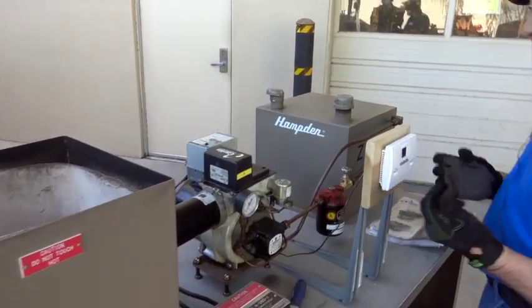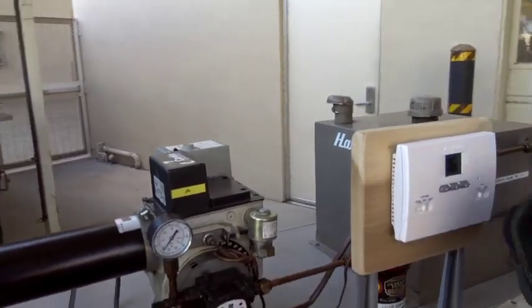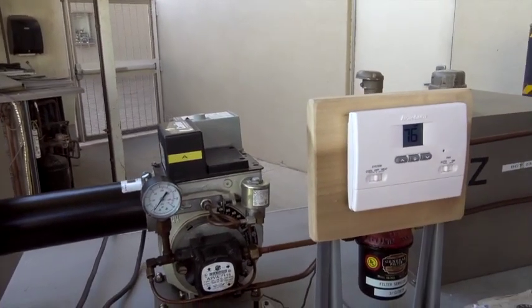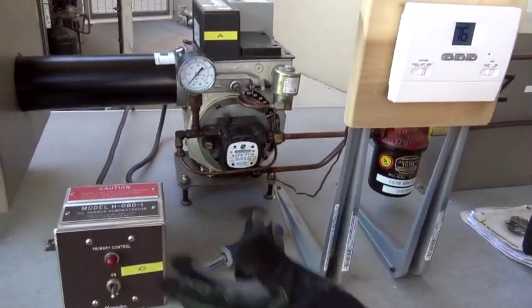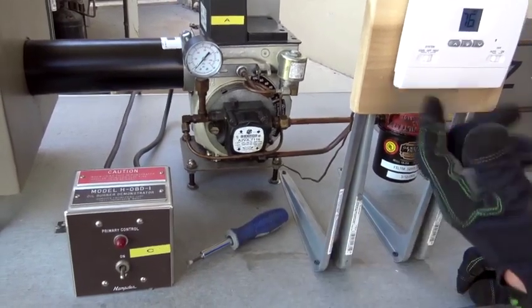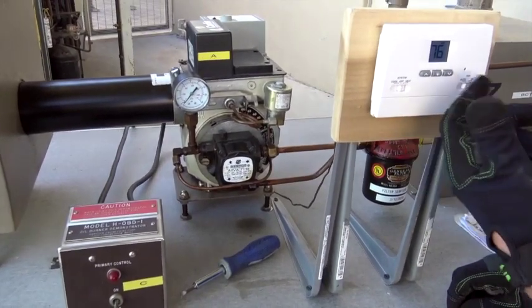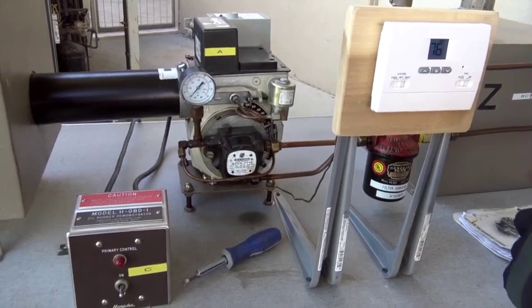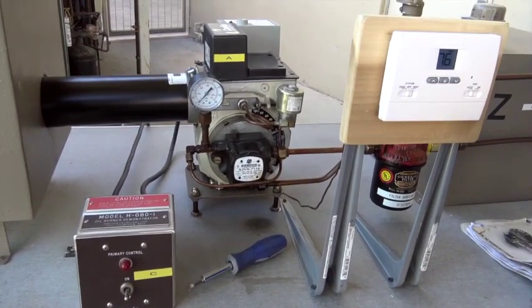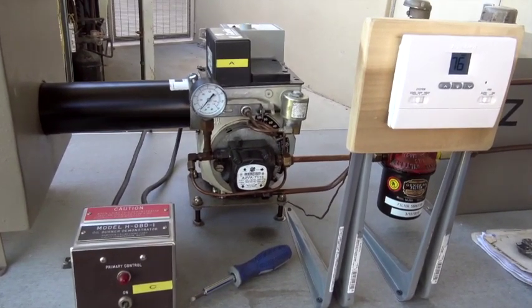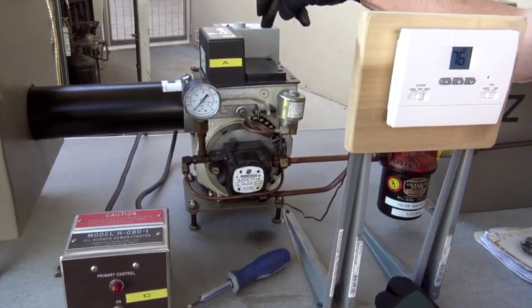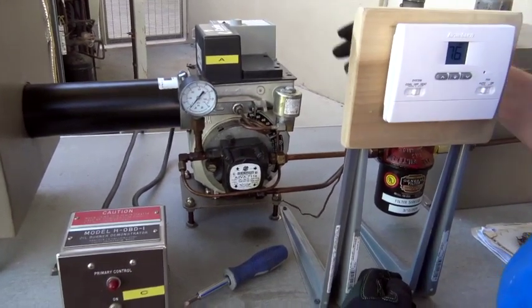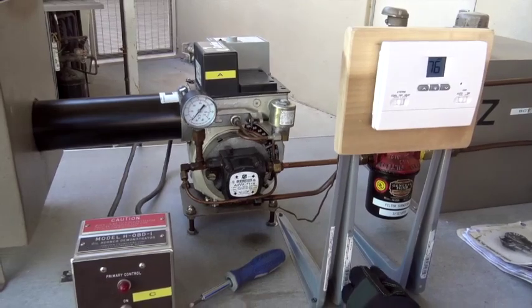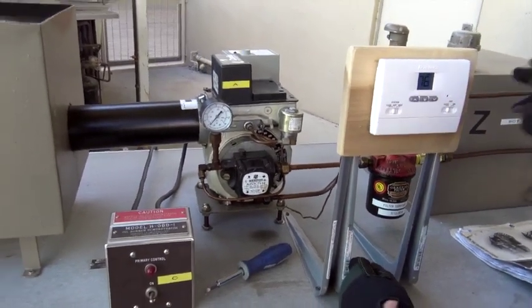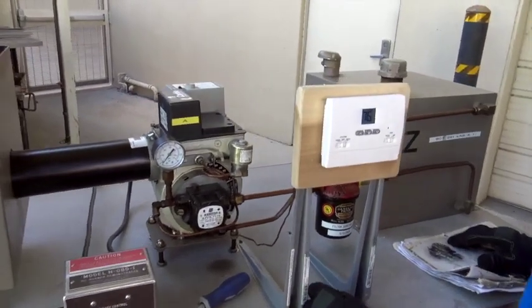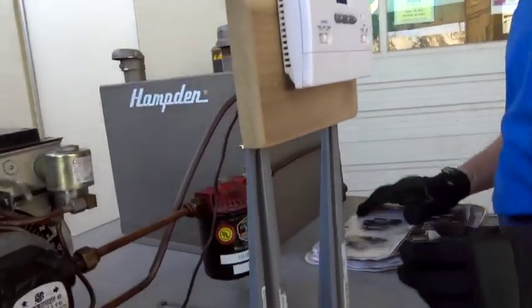Now this is our thermostat, which operates everything here. Naturally, you understand thermostats. That's our on-off control switch, primary control switch. We're eventually going to set this to heat. It's an electronic thermostat. We're going to set it above the set point to get this thing fired up, and that's going to send the signal to the control board. We're ready to go. It's going to start up the combustion air, and off we go. But I'm going to do a little bit on the fuel now, the most important part.